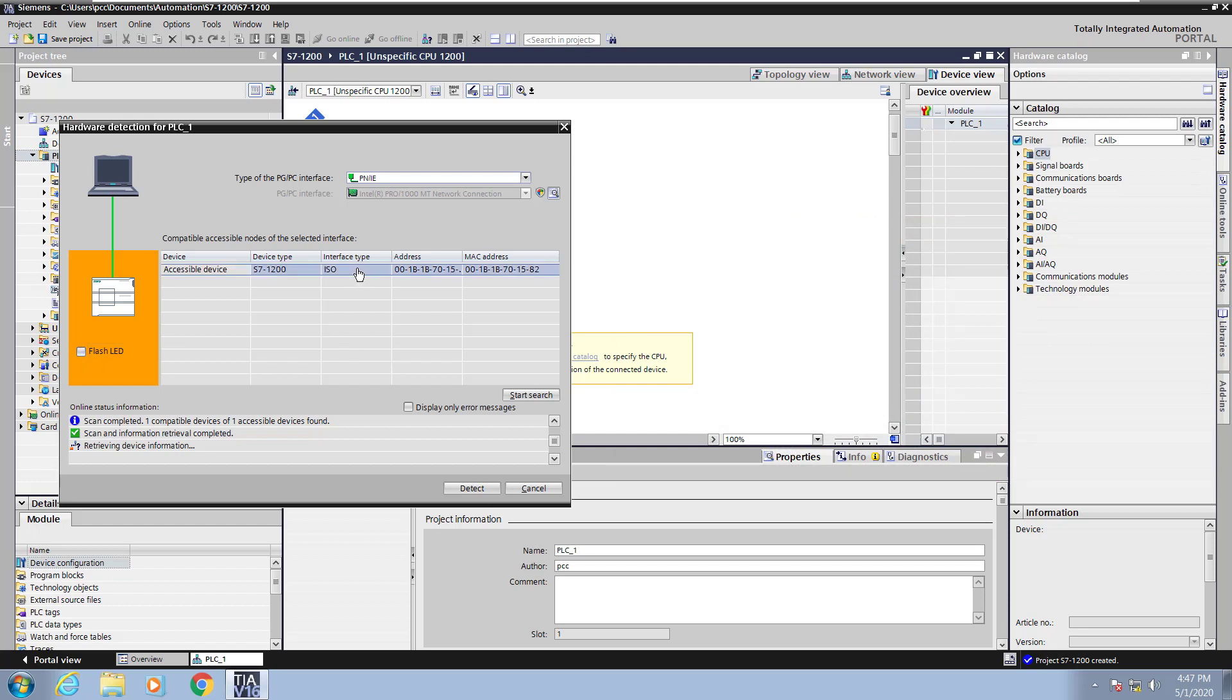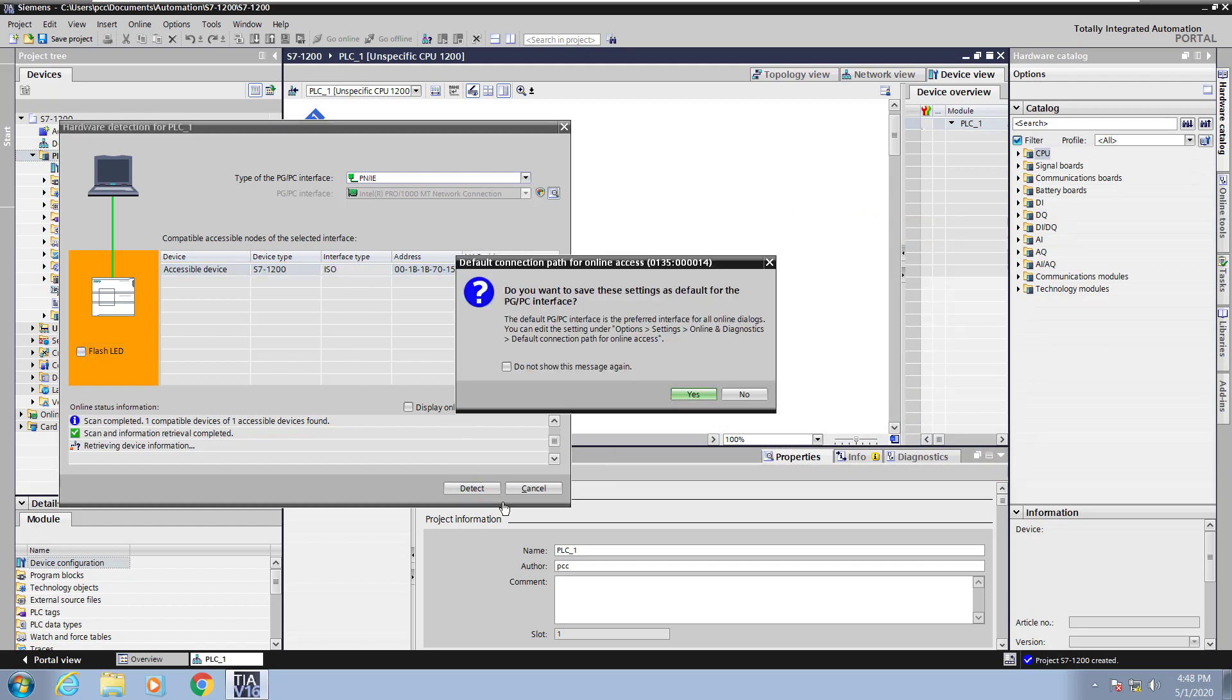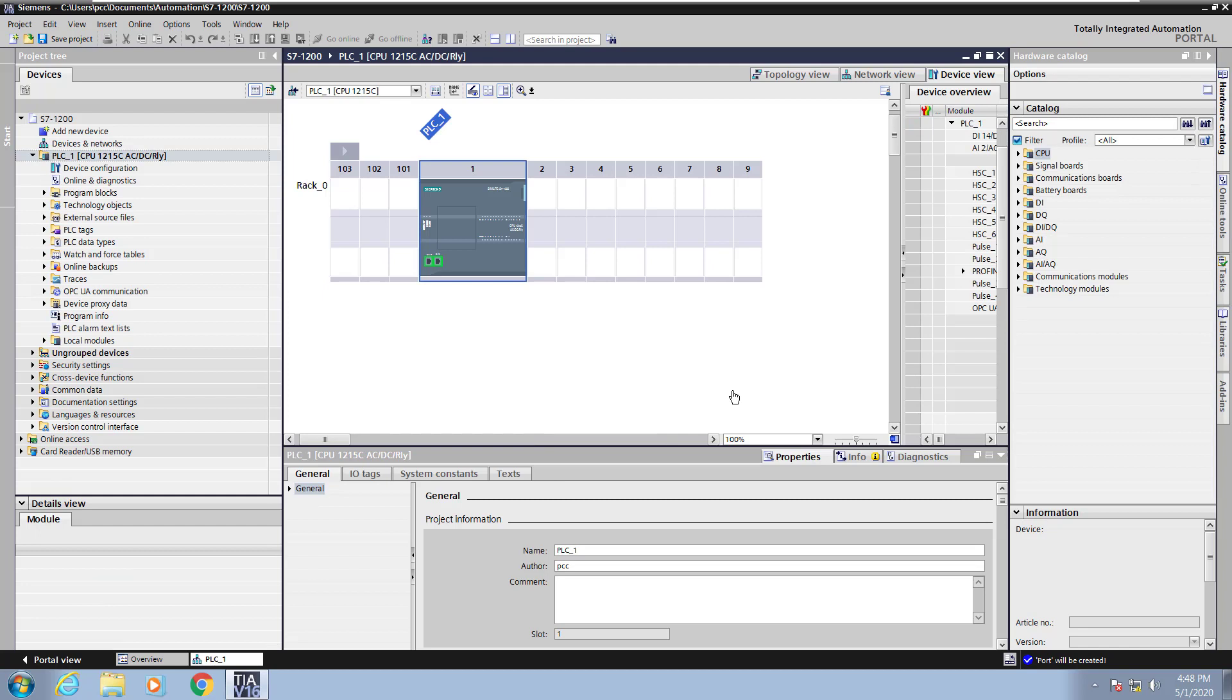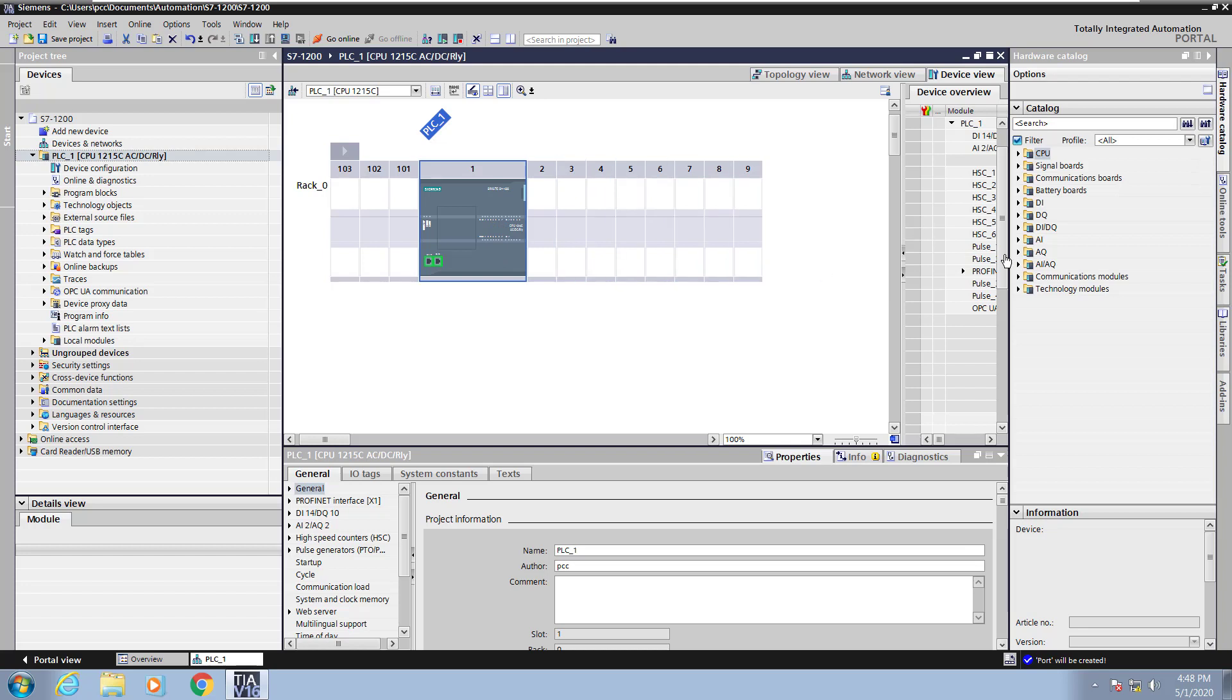Next I will press detect to start the detection process. Now I am prompted if I want to save my PG/PC interface settings. So you have a choice to say yes or no. I will say no at this point. The hardware configuration will be read out of the PLC so all of the part numbers that are included in your actual hardware configuration will be brought in with their default parameterization.